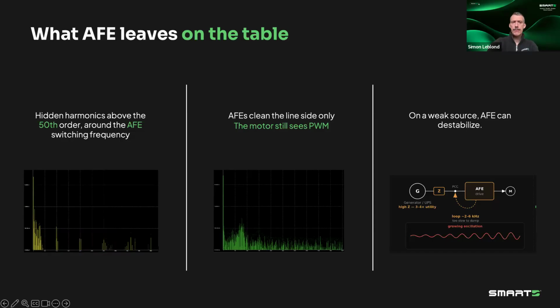We've talked about IEEE 519 and how it measures only up to the 50th order. Typically with an AFE, you have these spikes, and you can see it here on the capture, beyond the 50th order, clustered around the AFE switching frequency. So these are hidden harmonics that will not be captured by studies that are just looking at the first 50 orders. That doesn't mean they don't exist, and it doesn't mean they don't produce heat and potentially other interactions. They're just not captured by the current standard. If you're only concerned with compliance to IEEE 519, then you don't need to consider them for now, until the next revision. If you're concerned with total harmonic distortion, then those are real.